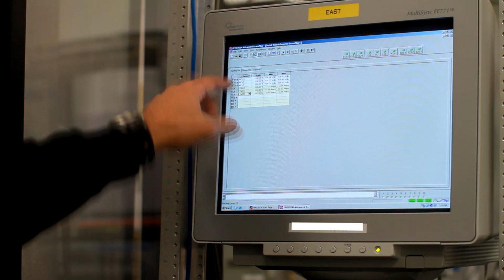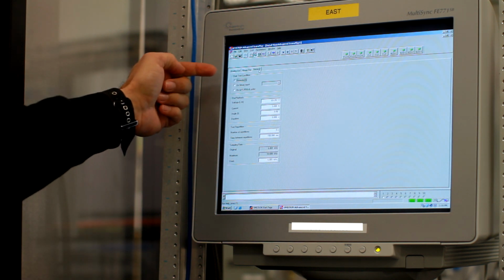Okay, now that that's complete, we also want to go into the analog out tab of this view. We want to go to General to make sure we're set up properly. Right here, on the top radio buttons, you have a start test condition. Right now it's defaulted to immediately. So what we want to do is trigger on the IRIG-B pulse or the GPS pulse, so we select that radio button. We've done the traces, making sure we have the correct roll and all.